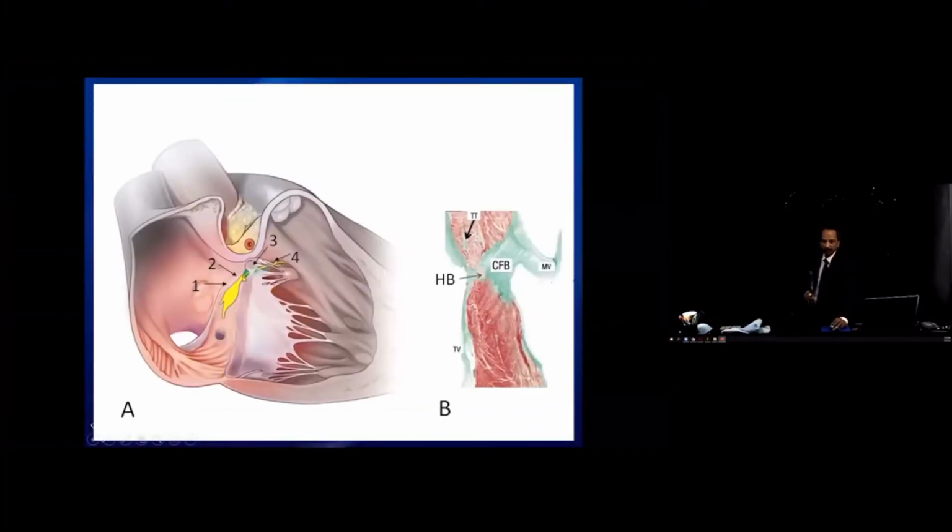If we target this region, the nice thing is we're not messing with the tricuspid valve at all. That's a plus. The other nice thing is that we don't have to go through a thin part of the septum like the membranous septum. So that's probably a plus. We have a little bit broader target, but the downside is that the more proximal you come, the more likely you're going to sense atrial electrograms. And if those are large, they're going to mess with the timing cycles. Certainly all of these have been observed both ways.